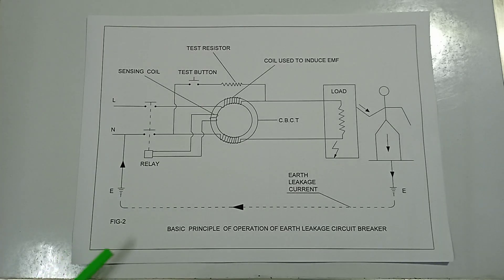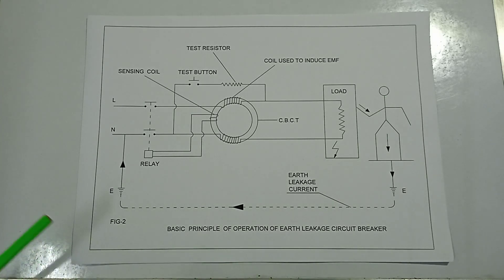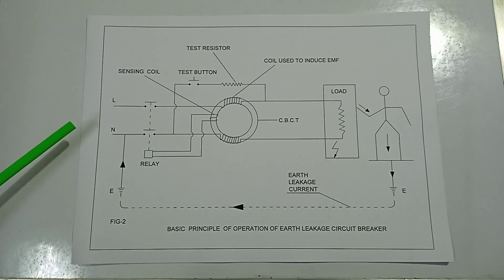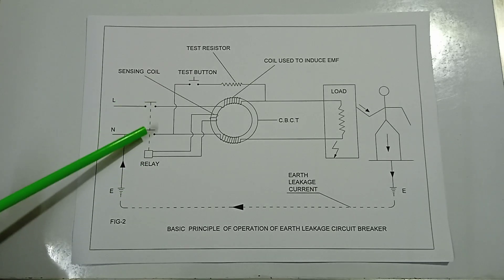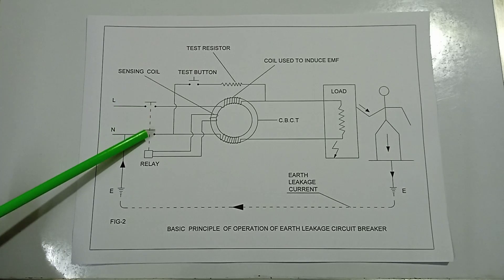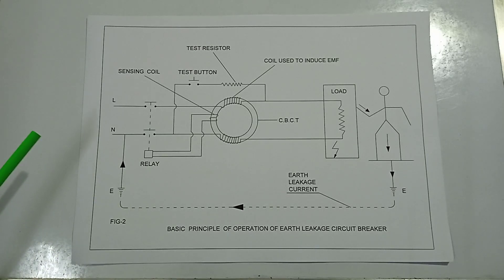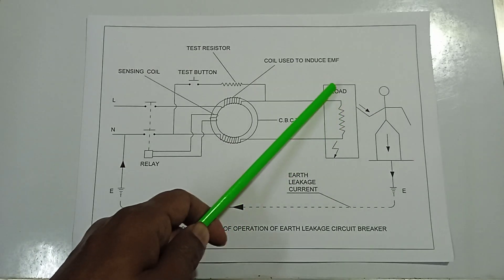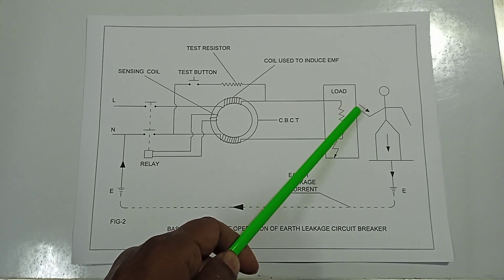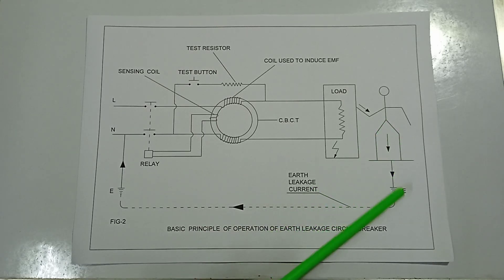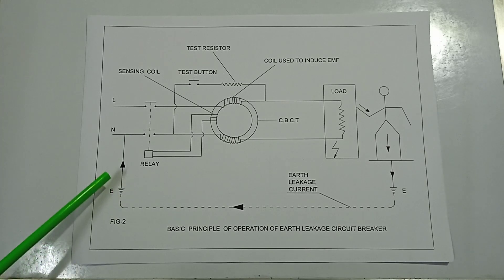Figure 2 shows the basic principle of operation of an earth leakage circuit breaker in a double-pole configuration, with line and neutral conductors, the relay, and the breaker contacts. When an earth fault occurs — for example, when a human touches a live conductor — the current passes through the earth and returns to the neutral, creating an imbalance in the primary circuit of the current transformer.